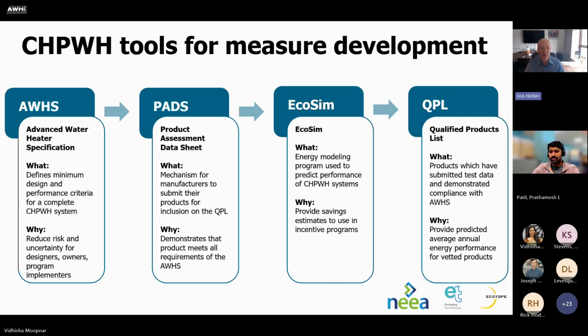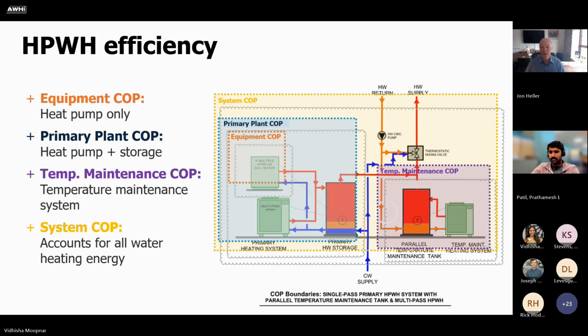Click one more time. So that system COP is different than just the equipment COP, which would be the heat pump only. It's different from what you'd call the primary plant COP, which includes the impact of the storage tanks. It also includes the COP of whatever system you're using to provide temperature maintenance or reheat the recirc load.